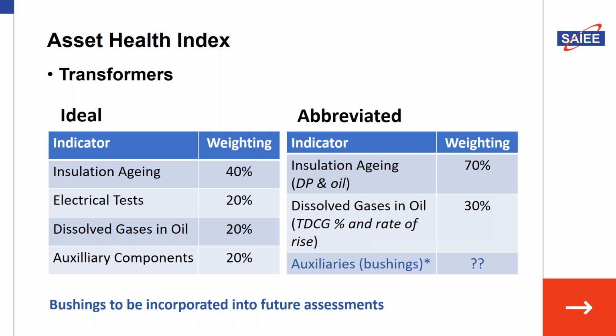So generally, we use what are called abbreviated tests, and recently in ESCOM we've been using the insulation aging taken from the DP paper samples as well as the oil, and also dissolved gases - called total dissolved combustible gases. We look at their prevalence in percentage as well as the rate of rise since we last measured, and so on.